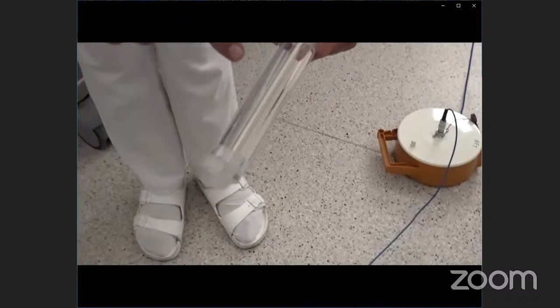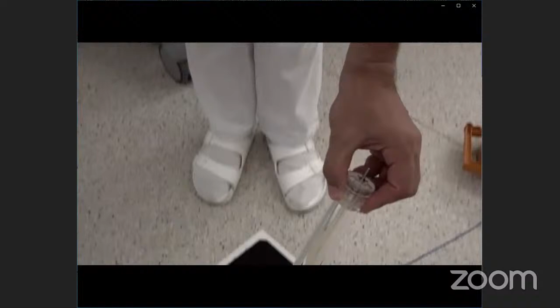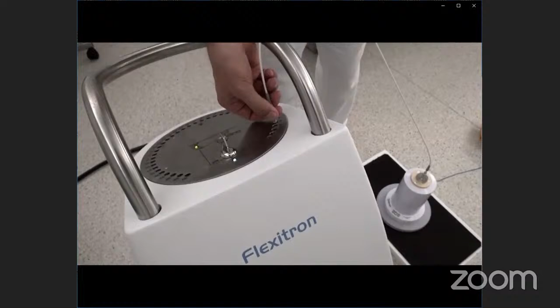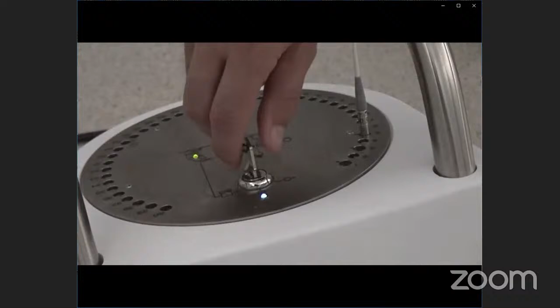And there is a special insert which accommodates the source. During the measurement, the source will be positioned in the center of the insert. Here I put the insert into the chamber and connect it to the transfer tube. The other end of the transfer tube is inserted in one of the channels of the afterloading machine. With a special key of the afterloader, it is switched to a position of ready for irradiation. This is the setup with the ionization chamber and the afterloader.